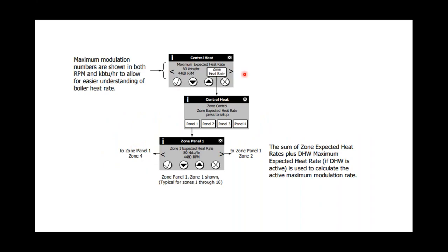We'll have a maximum expected heat rate of 80,000 BTUs. We'll click zone panel. It'll show up panel 1 through 4. We'll select panel 1. On panel 1, I can do zone 1 through 4, and I can set the firing rates for each one of those zones. It still gives you full priority. So if you have a home that has 4 zones of heat, we can use the panel for those 4 zones. The domestic hot water terminals on the boiler will still work, and always will still work.